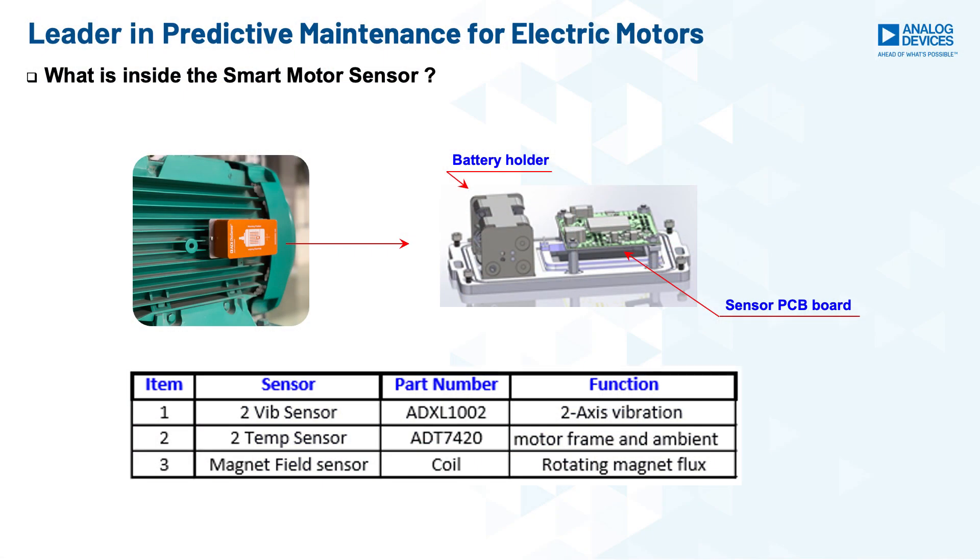For smart motor sensor device configuration in the field, the user has to use the mobile app. Inside the smart motor sensor, there are five high-performance sensors integrated, including two vibration sensors — the Analog Devices high-performance MEMS sensor ADXL1002 — to sense motor frame vibration in the XZ two-axis, two temperature sensors from Analog Devices ADT7420, where one measures motor frame temperature and another measures ambient temperature, and one magnetic field flux sensor with high bandwidth to sense motor rotation speed and some motor faults. Because of these integrated high-performance sensors, the smart motor sensor solution can diagnose nine motor faults at an early stage, which is a major differentiation from competitors.